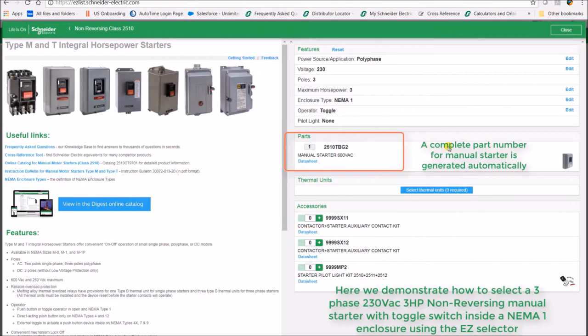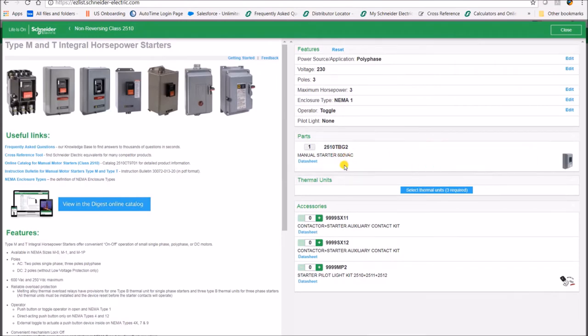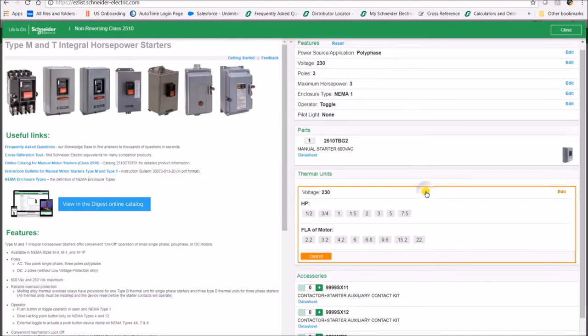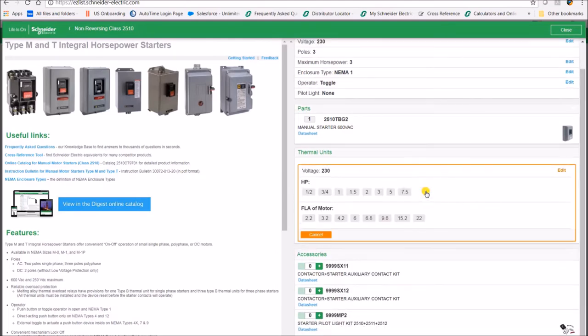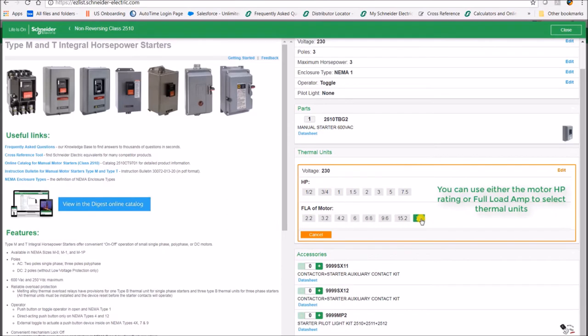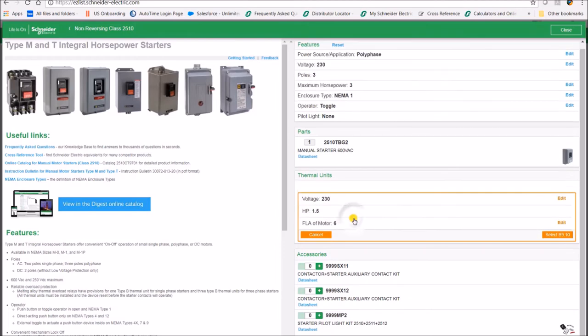A complete part number will automatically be generated. Thermal unit selection can also be done through the easy selector. Select based on your horsepower or the FLA of your motor. Once it is selected, a part number for the thermal unit will be generated.